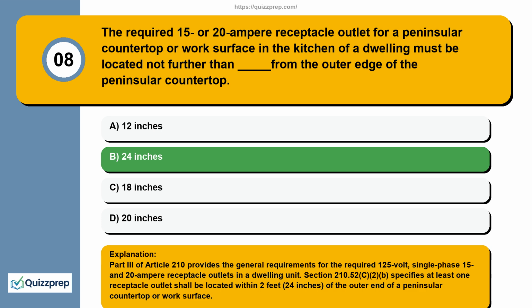Part 3 of Article 210 provides the general requirements for the required 125-volt, single-phase 15 and 20 ampere receptacle outlets in a dwelling unit. Section 210.52(C)(2)(b) specifies at least one receptacle outlet shall be located within 2 feet, 24 inches, of the outer end of a peninsular countertop or work surface.